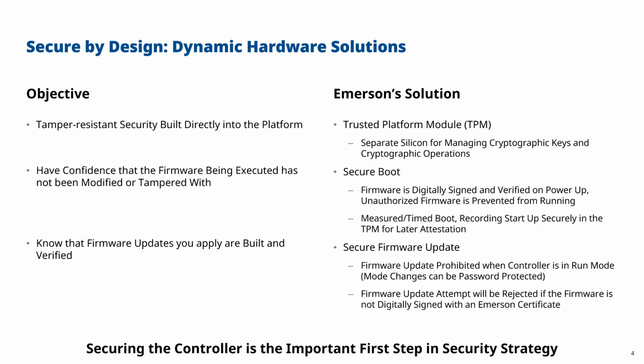When a firmware update is performed, any update attempt will be rejected if the firmware is not digitally signed with an Emerson certificate. There are various ways of doing this, including hashes and the certificates themselves. If it's not an official certificate, the firmware cannot be updated, which prevents various root type attacks on the controllers themselves.